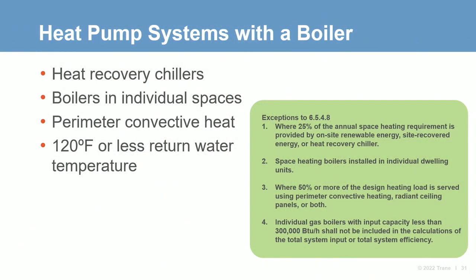Though this section describes the requirements for a gas boiler in a system, it could still apply to a heat pump system that has a boiler in it. The exemptions list for this section references heat recovery chillers, boilers in individual spaces, and perimeter convective heat, all of which may be applicable to our four-pipe system. Another applicable section here defines that coils and heat exchangers must be selected to develop 120 degrees or less return water temperature to the boiler.